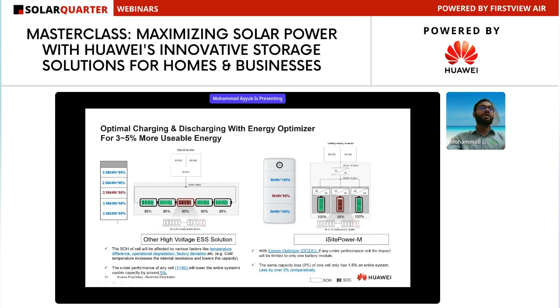Take this example: on the left hand side we have a traditional solution. If there is some issue in one pack, let's say the middle pack, and it's not able to charge to 100%, because all these packs are in series, we have to stop charging all the packs, since they do not have the capability of independent charging or discharging. But in our case, if that pack has a fault and stops at 95%, we can bypass it and continue to charge the remaining packs.